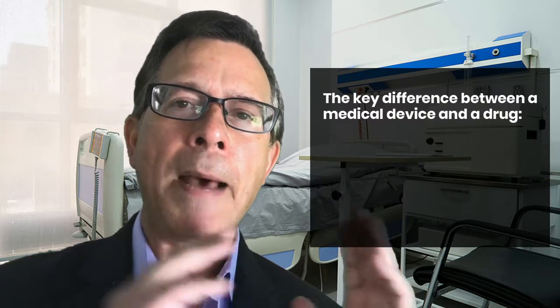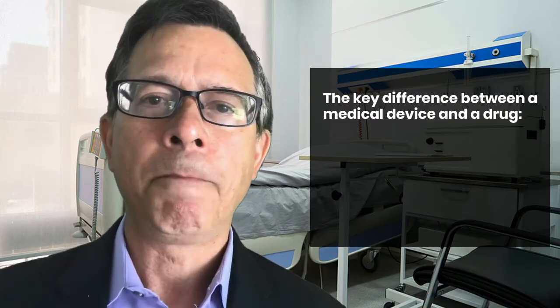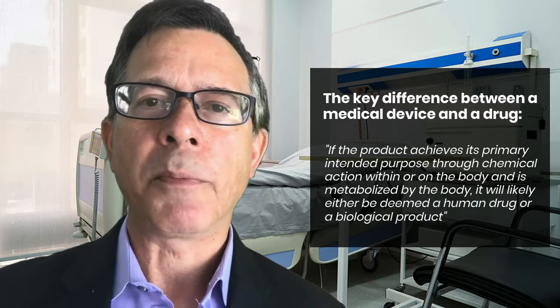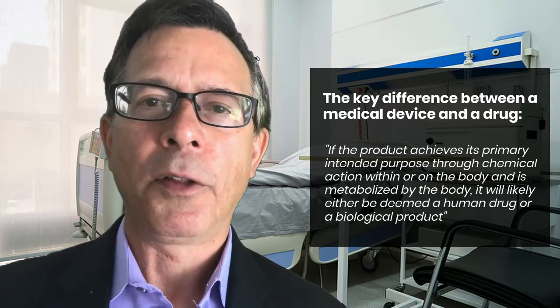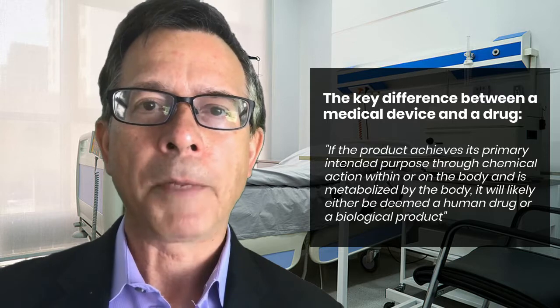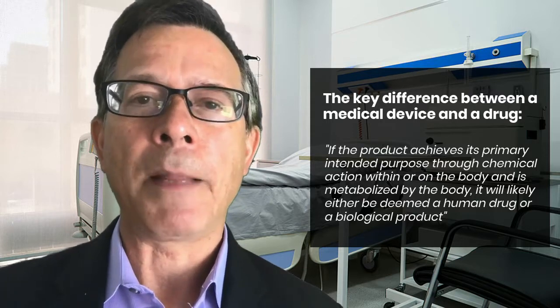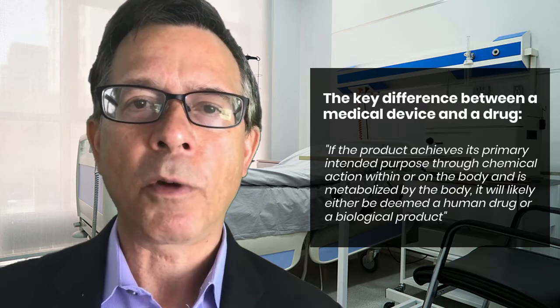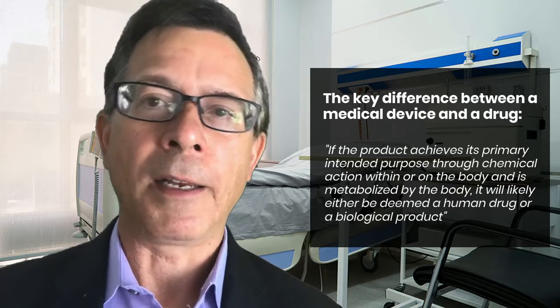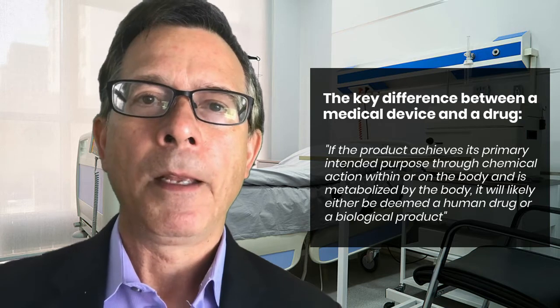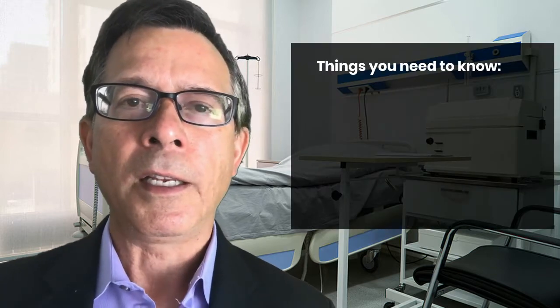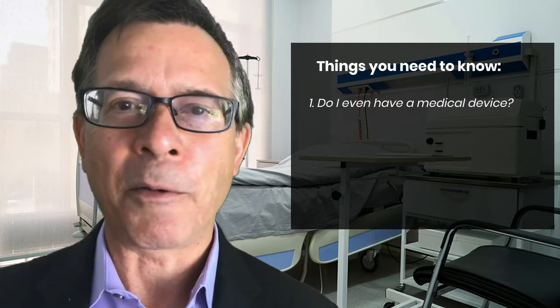The key difference between a medical device on one hand and a drug on the other is this. If the product achieves its primary intended purpose through chemical action within or on the body, and it's metabolized by the body, it will likely either be deemed a human drug or a biological product like aspirin or a vaccine. Now, all medical devices are subject under FDA rules to establishment, registration, medical device listing, quality system regulation, labeling requirements, medical device reporting, and other controls. So the first thing you need to know is, do I even have a medical device? Because that's a lot of regulation.